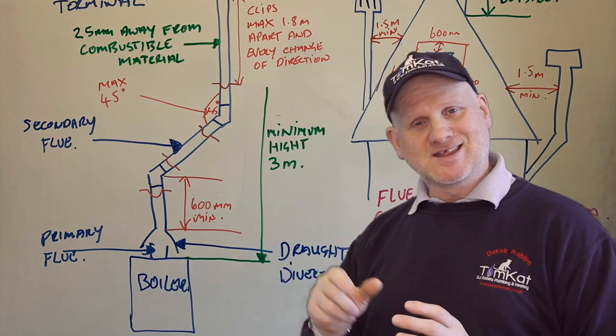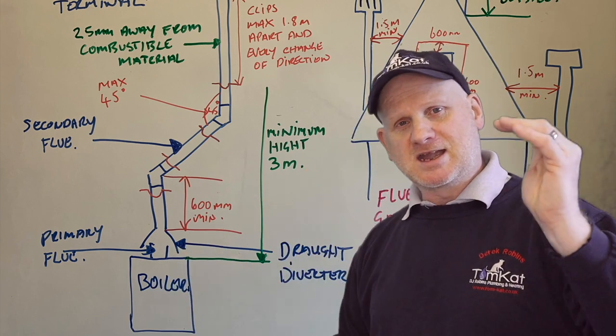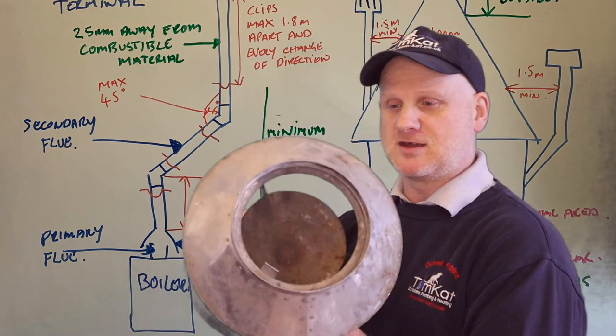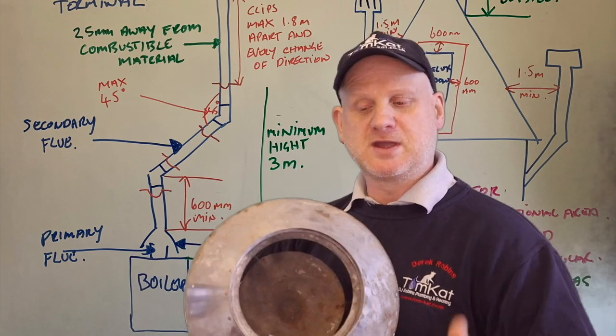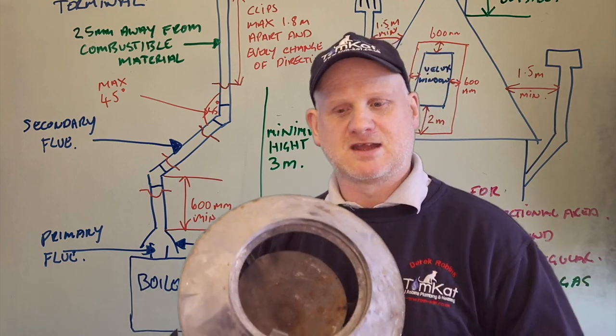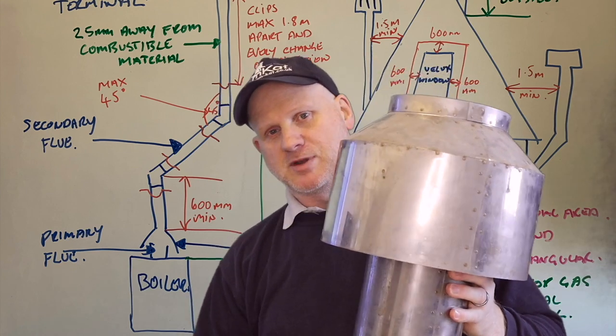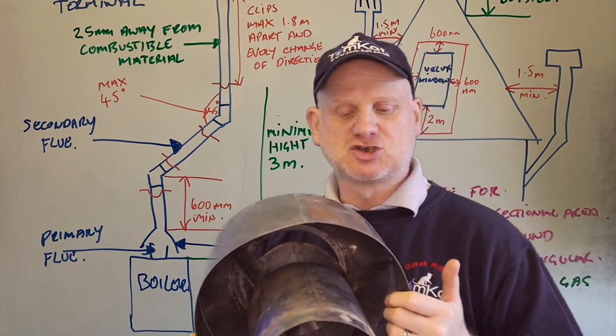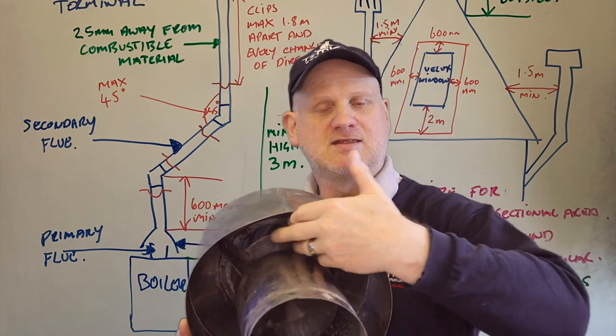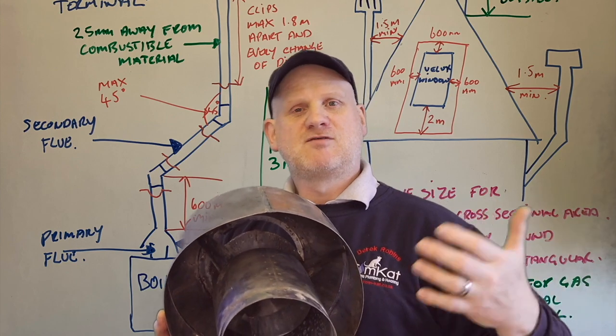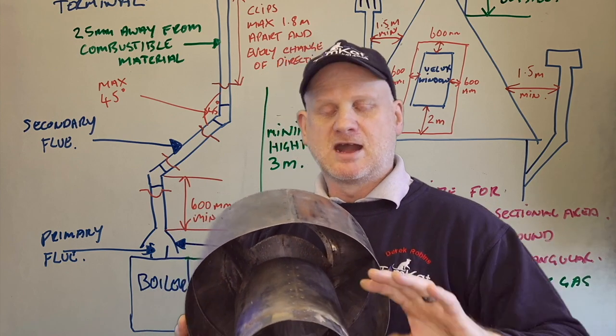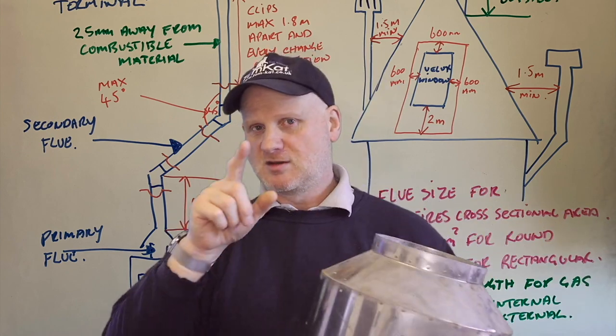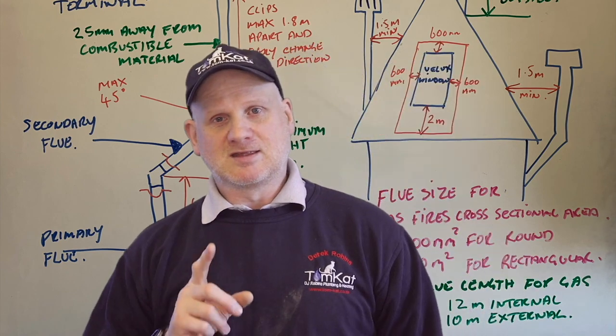The draft diverter is incredibly important. It can either be external like this one shown here. You can see this is where the flue would be connected, and you can see the baffle on the inside. This is where it would be connected to the appliance. This is where we would do the flue flow test and spillage. If we have excessive pull, this is where it would be broken. If we need to dilute the air, this is where it comes in. If we have downdraft, it would come out here. A lot of them are built into the appliance.